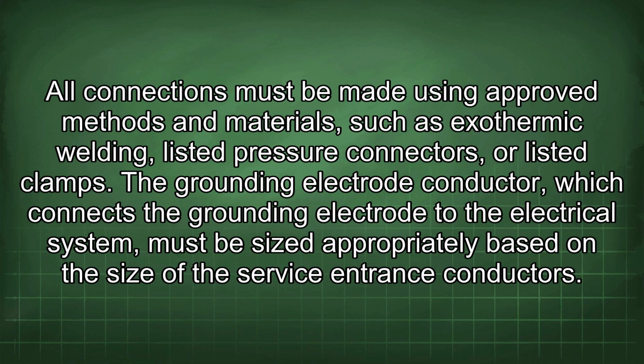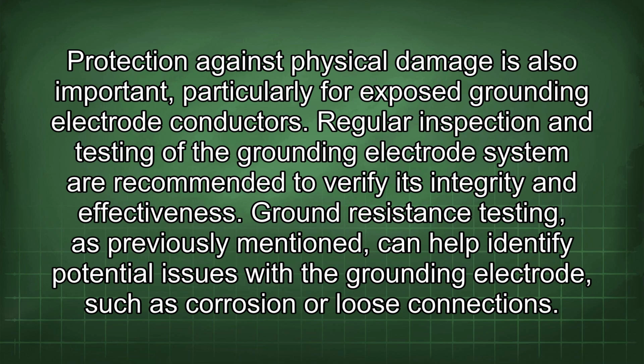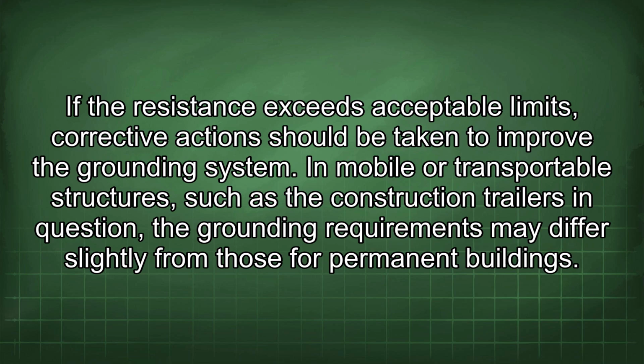All connections must be made using approved methods and materials such as exothermic welding, listed pressure connectors, or listed clamps. The grounding electrode conductor, which connects the grounding electrode to the electrical system, must be sized appropriately based on the size of the service entrance conductors. Protection against physical damage is also important, particularly for exposed grounding electrode conductors. Regular inspection and testing of the grounding electrode system are recommended to verify its integrity and effectiveness. Ground resistance testing, as previously mentioned, can help identify potential issues with the grounding electrode, such as corrosion or loose connections. If the resistance exceeds acceptable limits, corrective action should be taken to improve the grounding system.